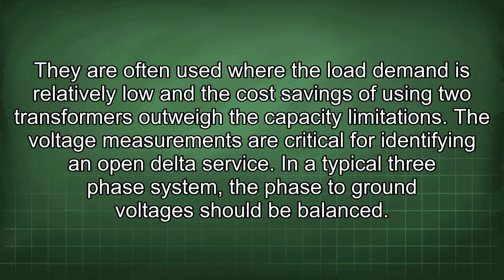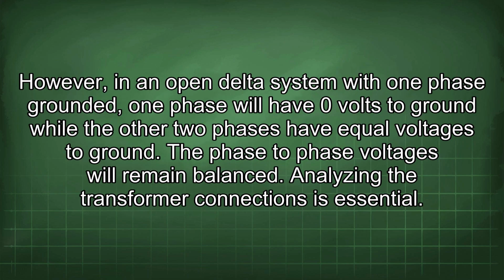In a typical three-phase system, the phase-to-ground voltages should be balanced. However, in an open delta system with one phase grounded, one phase will have 0 volts to ground while the other two phases have equal voltages to ground. The phase-to-phase voltages will remain balanced.